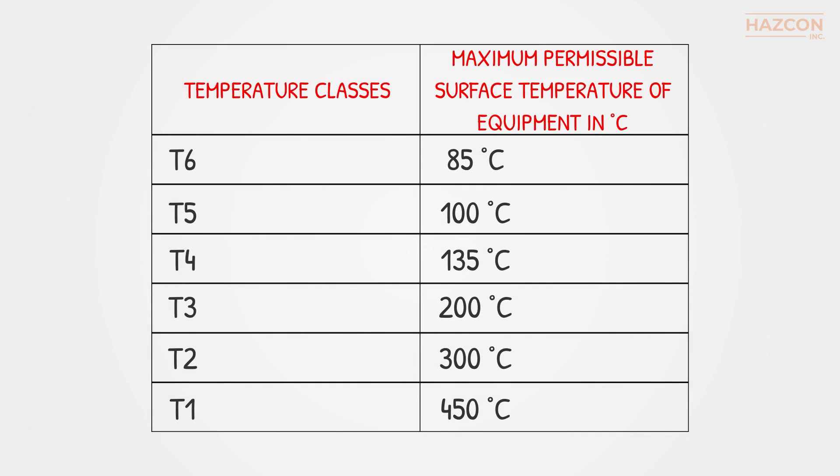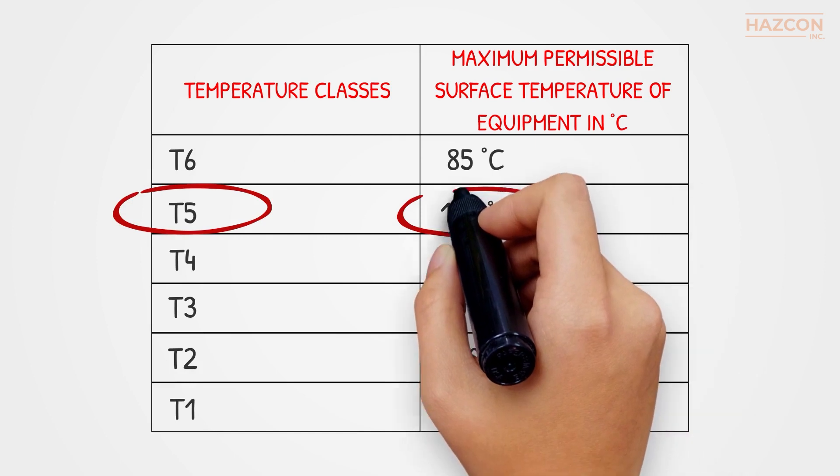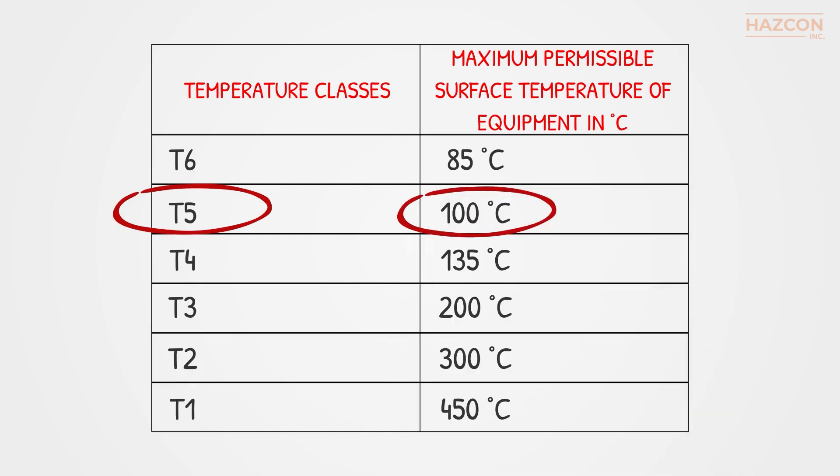What this table means is that a device classified as T5 will never retain a surface temperature higher than 100 degrees Celsius, which can be exposed to explosive atmospheres and cause an explosion.